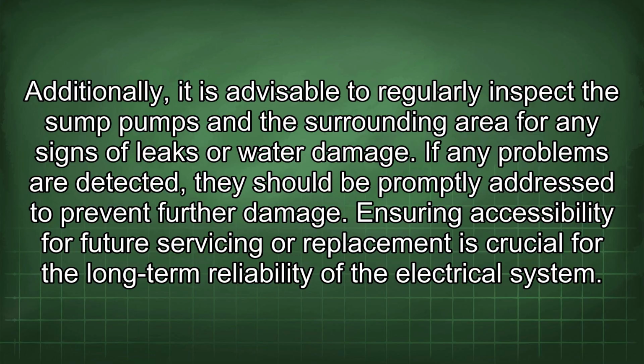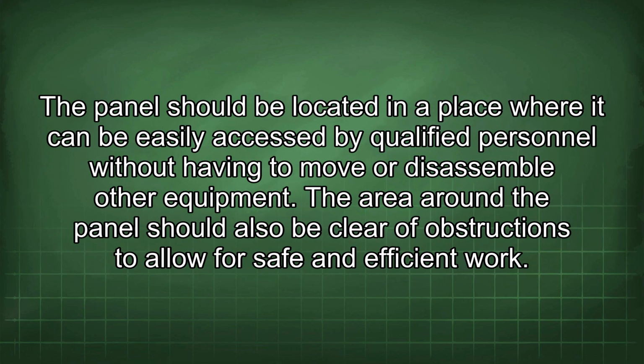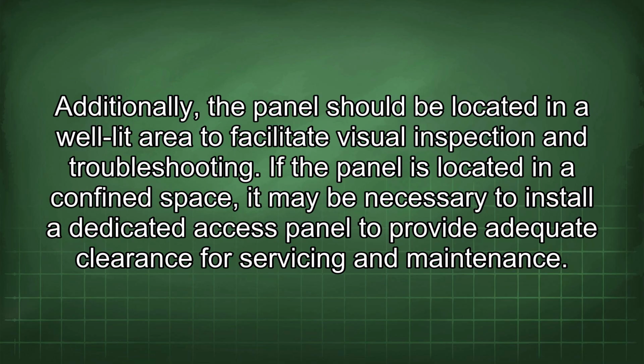Ensuring accessibility for future servicing or replacement is crucial for the long-term reliability of the electrical system. The panel should be located in a place where it can be easily accessed by qualified personnel without having to move or disassemble other equipment. The area around the panel should also be clear of obstructions to allow for safe and efficient work. Additionally, the panel should be located in a well-lit area to facilitate visual inspection and troubleshooting. If the panel is located in a confined space, it may be necessary to install a dedicated access panel to provide adequate clearance for servicing and maintenance.